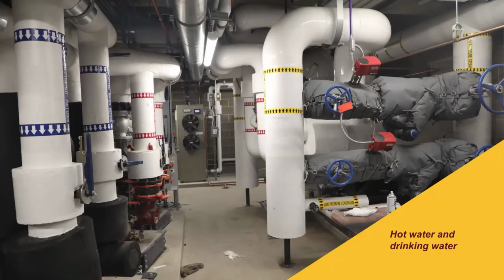The main mechanical space on this level takes the campus utilities on the right-hand side—high-pressure steam from the main heating plant—through a reducing station, which lowers the pressure of the steam so it condenses, cool enough to exchange heat and bring water hot enough to run the perimeter heating, the old radiators. That's an energy and cost savings for the campus.